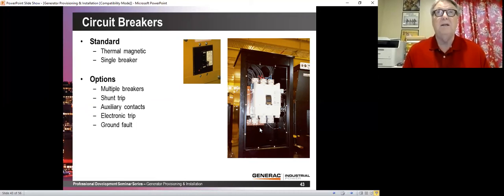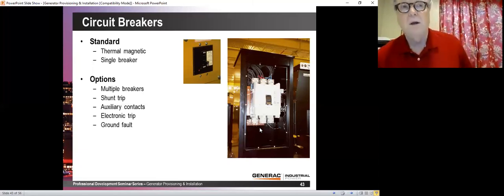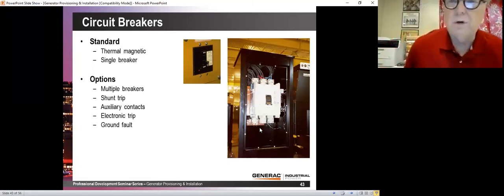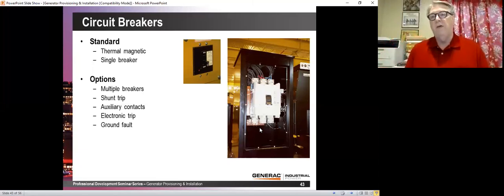If you were to take it out of the generator and put it into a switchboard, then it follows the 80% rule for switchboards. But in the generator it is UL tested at 100%, so I don't see any reason to spec a 100% breaker. Typically, LSI breakers are also kind of a waste of money. For the cost of an LSI 100% breaker, you can upgrade to a sound level 2 enclosure, and I would much rather have that. Typically, these breakers never trip.